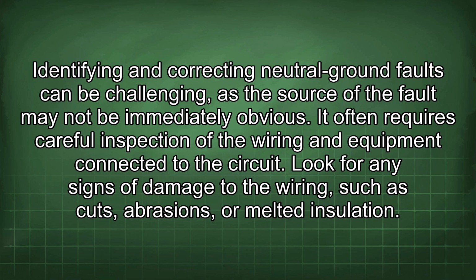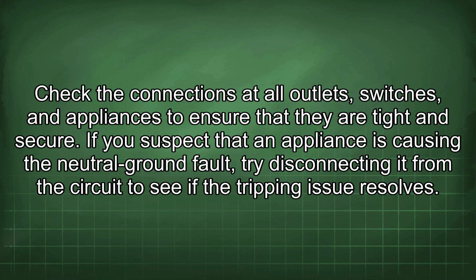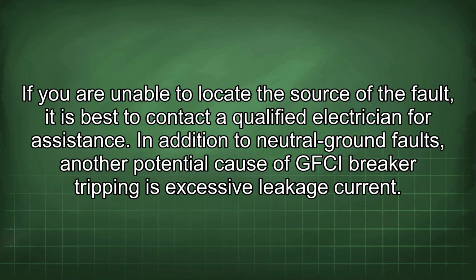Look for any signs of damage to the wiring, such as cuts, abrasions, or melted insulation. Check the connections at all outlets, switches, and appliances to ensure that they are tight and secure. If you suspect that an appliance is causing the neutral ground fault, try disconnecting it from the circuit to see if the tripping issue resolves. If you are unable to locate the source of the fault, it is best to contact a qualified electrician for assistance.